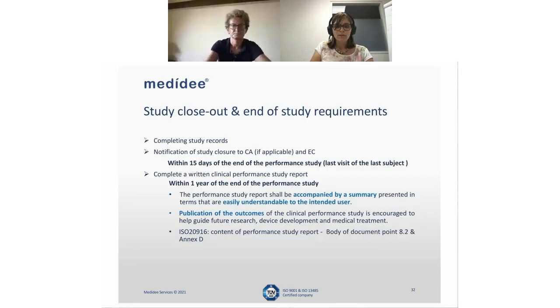Then when it comes to the end of the study, as a sponsor, you need to consider completing all the records, and then you need to as well notify the closure of your study to the competent authority, if applicable, and ethics committee, and this within 15 days after end of the performance study. And within 1 year after the end, you need to have written a formal performance study report, which illustrates what has been done. And here the content of such a report is as well documented in Annex D of the standard.